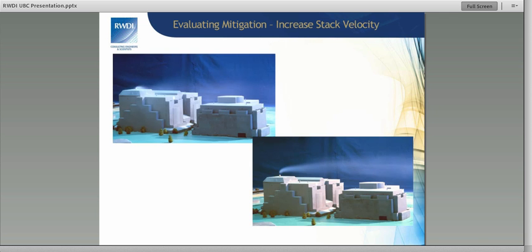We can also increase the exhaust velocity from the stack. Increasing the speed the effluent comes out gives more plume rise, so it shoots higher into the atmosphere, helping get it away and out of the wake zones we're worried about. This is usually only effective when starting from a low velocity—more and more designers are already designing stacks with high velocities. The downside to high velocity is it costs energy, and energy is something everyone is very interested in nowadays.